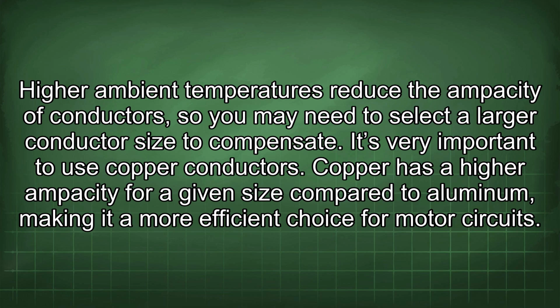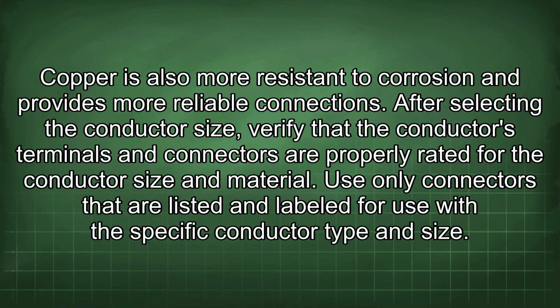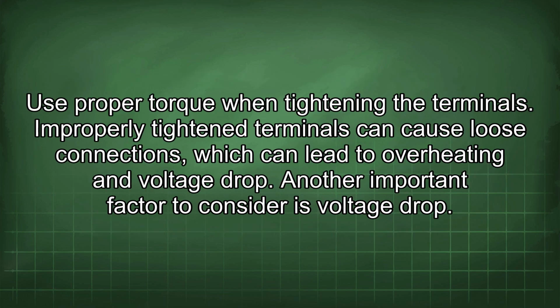It's very important to use copper conductors. Copper has a higher ampacity for a given size compared to aluminum, making it a more efficient choice for motor circuits. Copper is also more resistant to corrosion and provides more reliable connections. After selecting the conductor size, verify that the conductor's terminals and connectors are properly rated for the conductor size and material. Use only connectors that are listed and labeled for use with the specific conductor type and size. Use proper torque when tightening the terminals. Improperly tightened terminals can cause loose connections, which can lead to overheating and voltage drop.